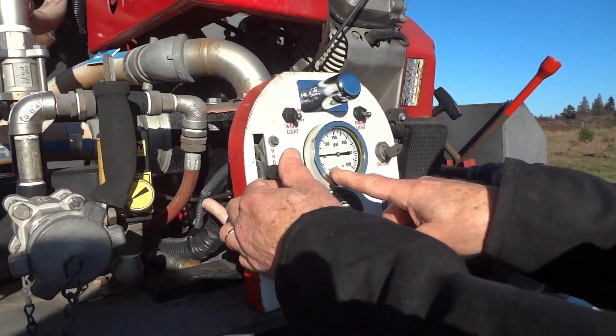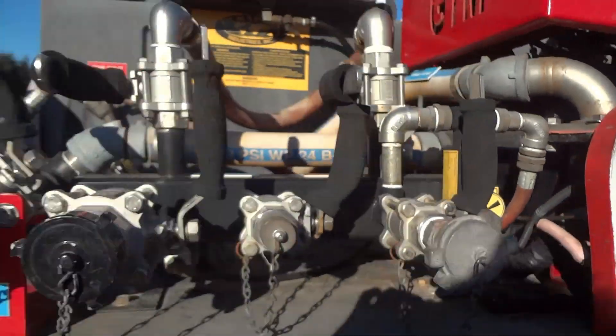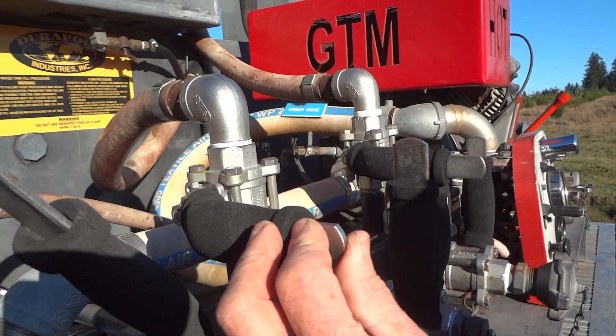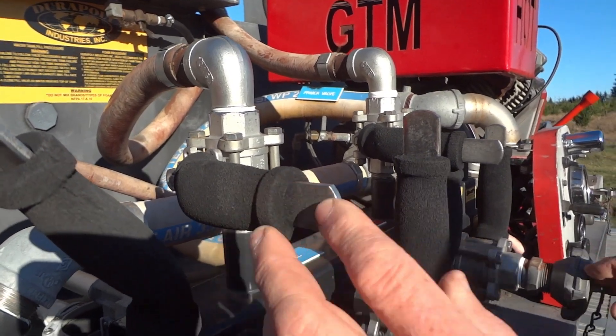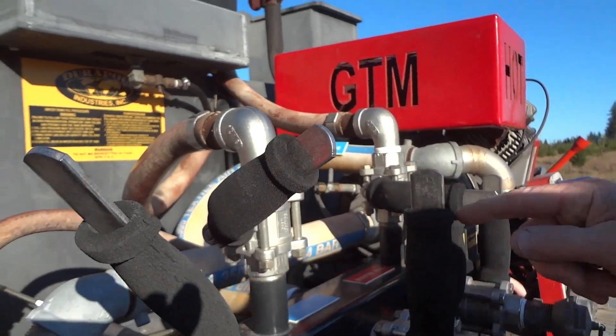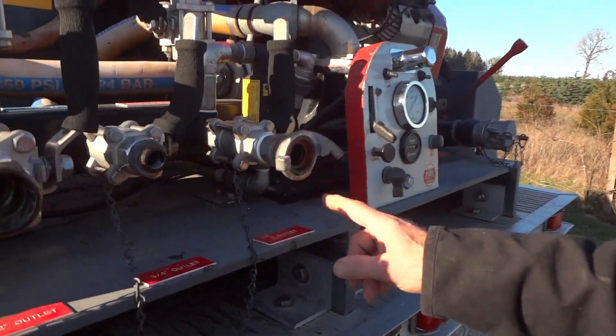You can see we have some pressure, so it's fully primed. This is a bypass — it needs to be off unless you're idling for an extended time, then crack it a little so that the pump won't overheat. Alright, we're going to demo these discharges.